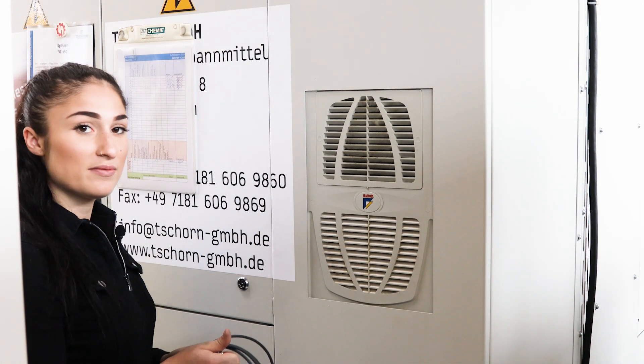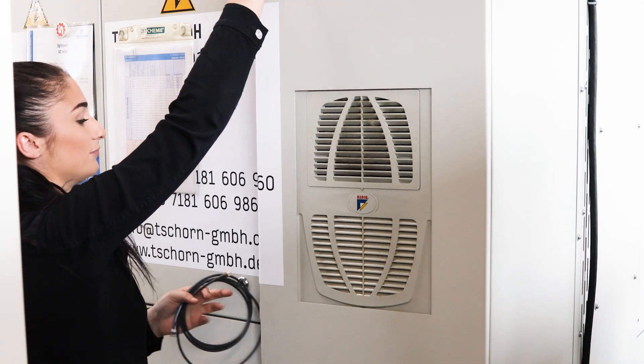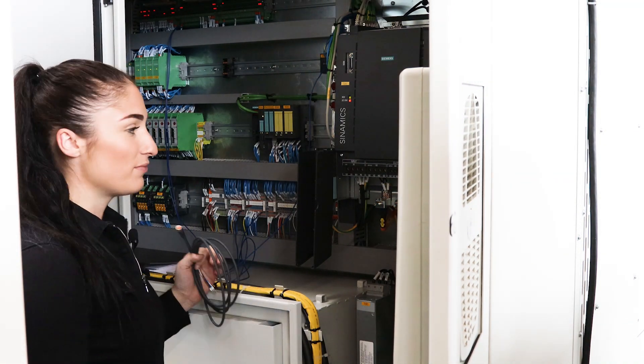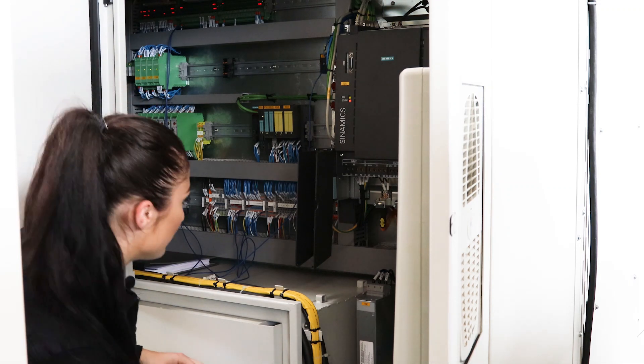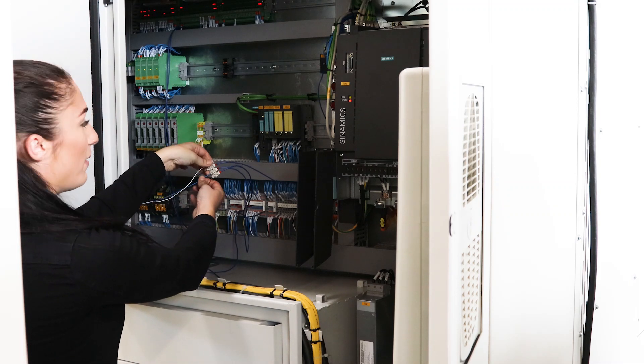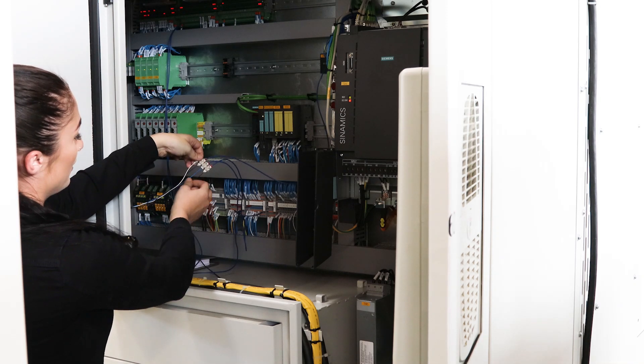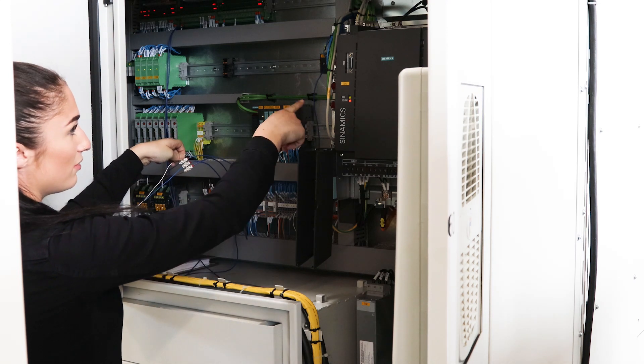For connecting, I first open the switchboard. I already prepared it and asked a colleague from electrics for help. He did the connection and said it's really simple. As you can see, the brown and the blue cable are for the power supply for the receiver — the 24-volt power supply. The black one here is a signal for the probe, which goes into the machine control.